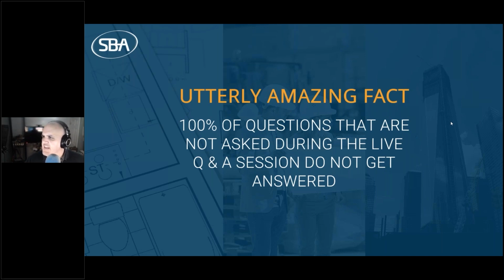Prior to retrofitting the HVAC system, how would one analyze or monitor the air quality of a building? Well, Keith, it really depends on what is in the building. I get asked this quite a bit. How do I determine that? And the challenge is if you have a pneumatics building, that's going to look completely different than if you have a DDC building. Or if you have a DDC building, so direct digital control building automation system from 2000, that's going to look completely different than a 2010 system. And that's just building automation and the sensing capacity and inputs and outputs, right?